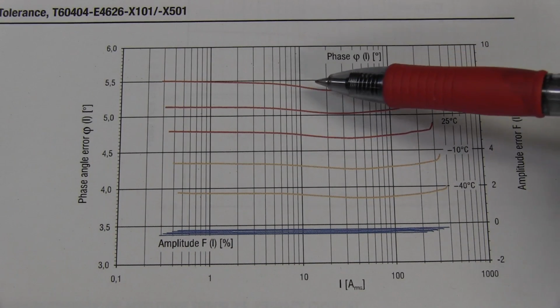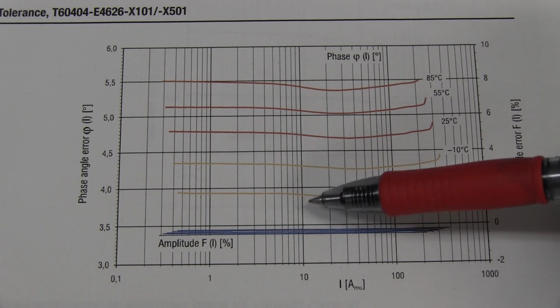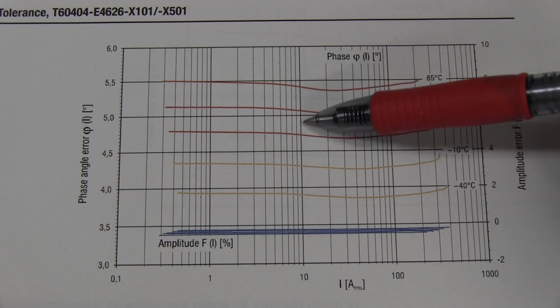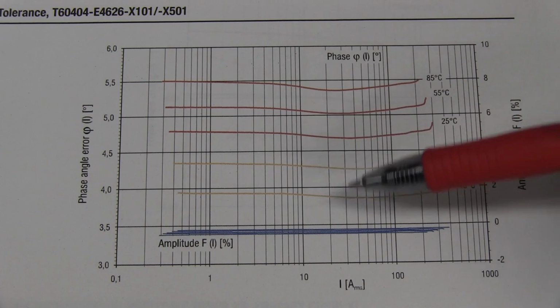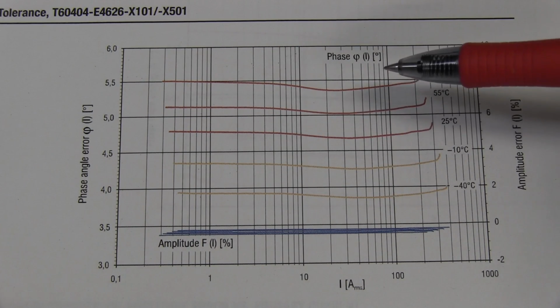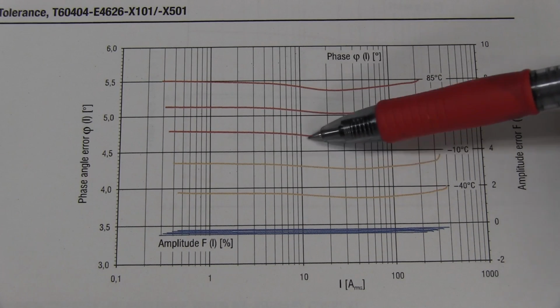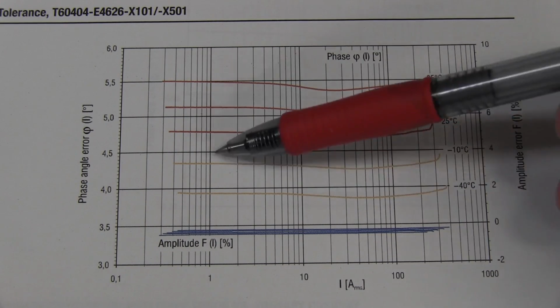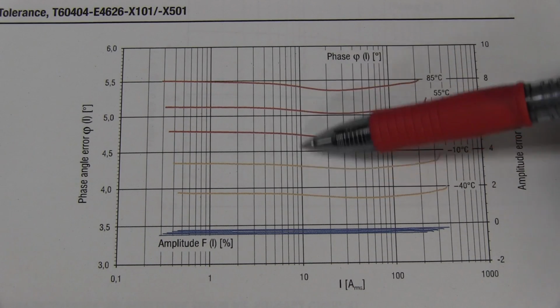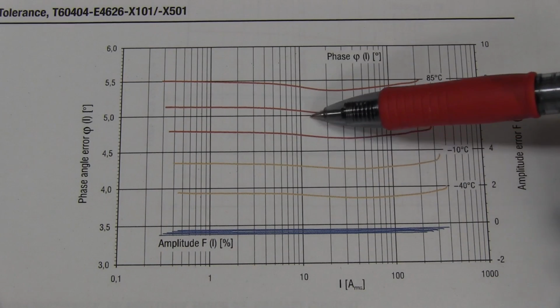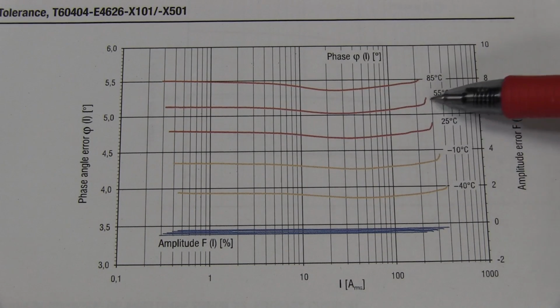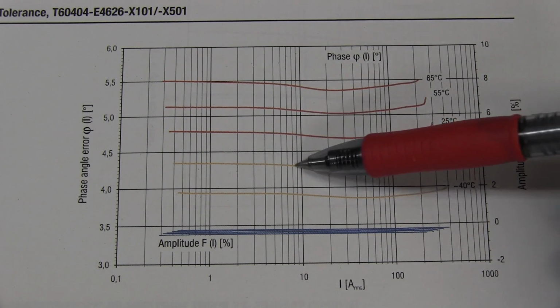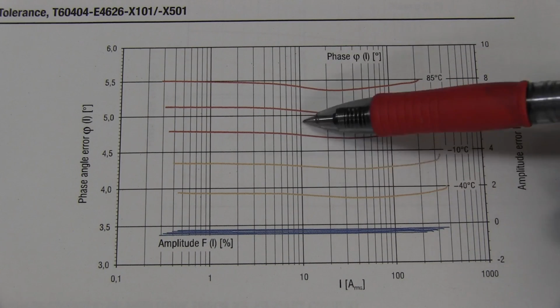These things accurately measure the phase angle as well, so they may even be taking the temperature into account. There might be a temperature sensor on the board, and they could compensate for this because it's fairly linear with temperature, over an operational range of say 55 down to minus 10, over that sort of 50 degree range.